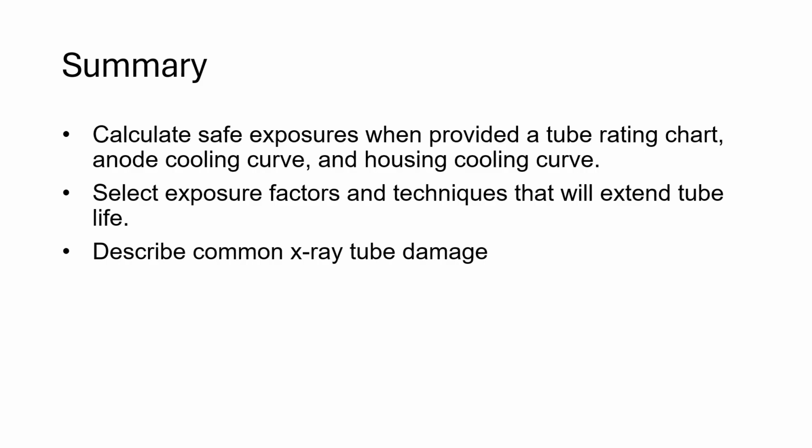And the way that you do that is either setting techniques that are way too high, taking exposures too fast, and not allowing for adequate cooling time, or shooting a huge technique on an ice cold anode.